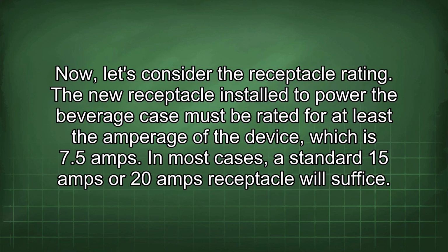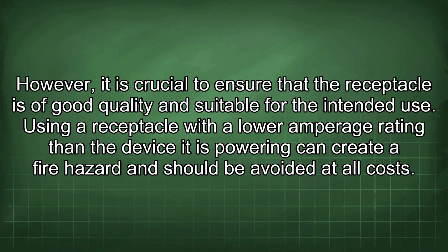Now let's consider the receptacle rating. The new receptacle installed to power the beverage case must be rated for at least the amperage of the device, which is 7.5 amps. In most cases, a standard 15 amp or 20 amp receptacle will suffice. However, it is crucial to ensure that the receptacle is of good quality and suitable for the intended use. Using a receptacle with a lower amperage rating than the device it is powering can create a fire hazard and should be avoided at all costs.